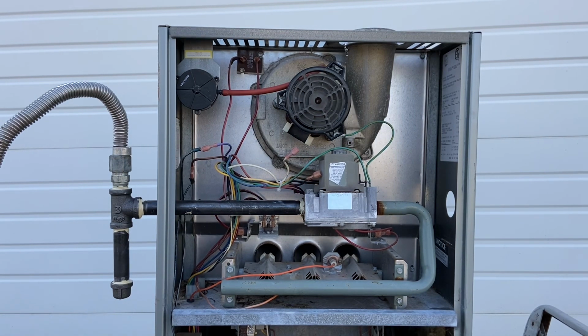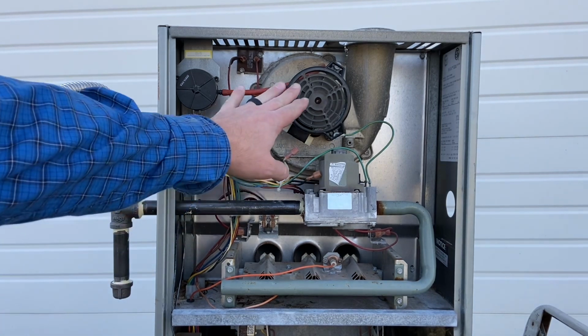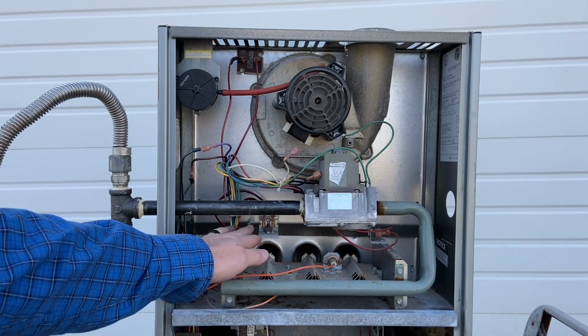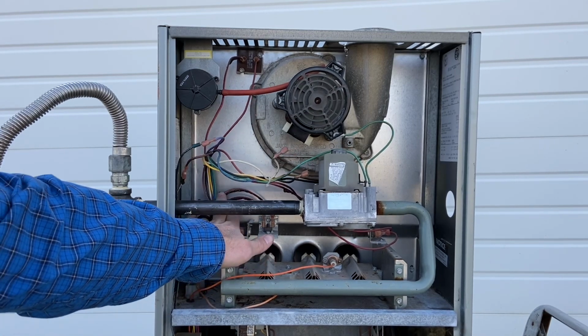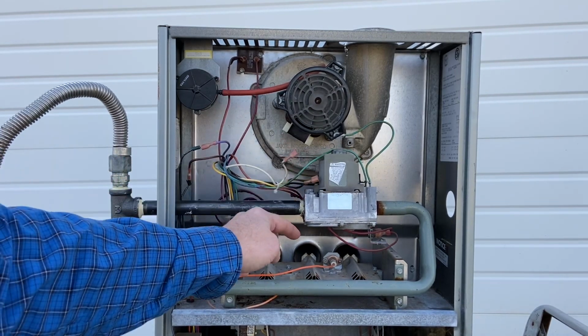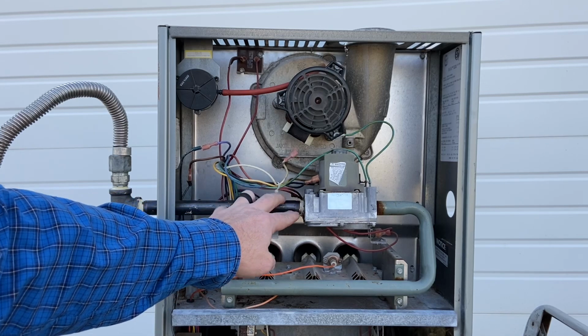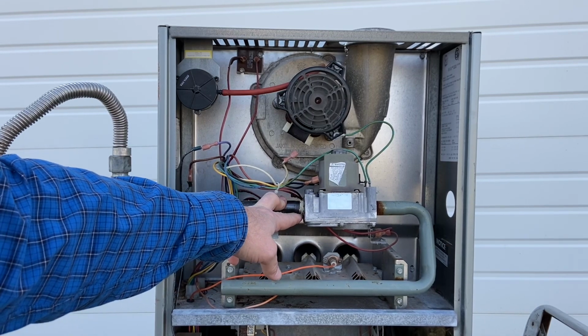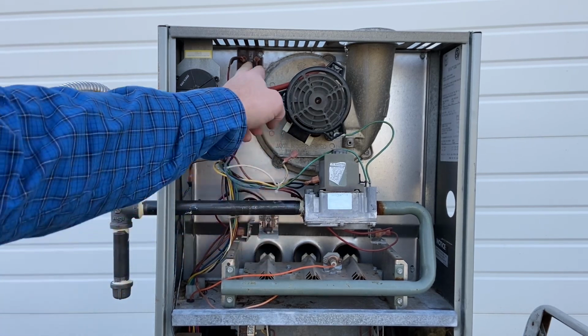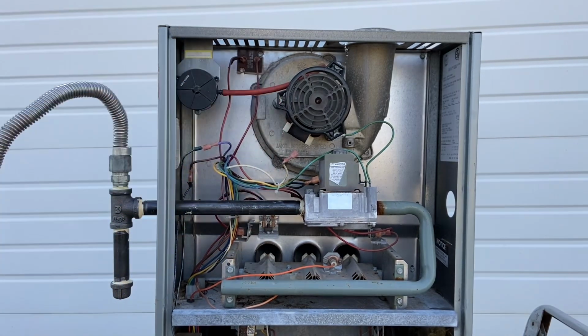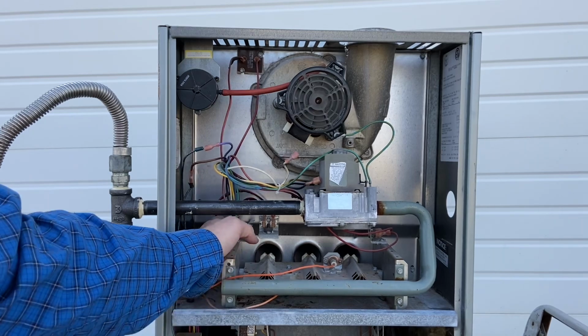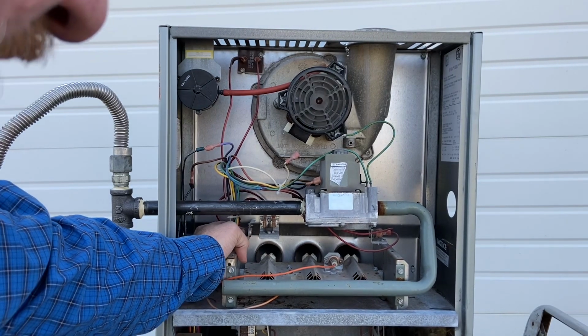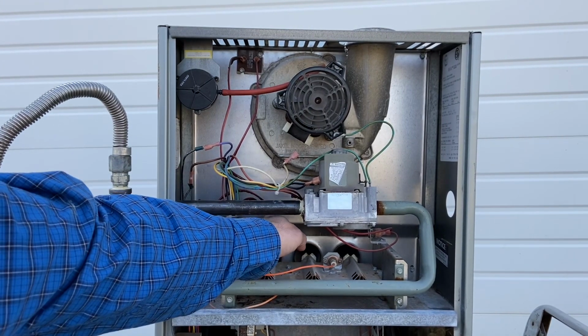So you can see there's a significant amount of time before the rollouts actually tripped on this furnace. That's how important this inducer draft motor is. We can see that there's a lot of charring going on. These wires have melted. They've melted here. There was a flame here because there was a small gas leak here where we didn't put new pipe thread compound on there to seal it. It burned all the way up to the top, and even our limit switch failed. It's all melted. The furnace is not running right now because these limits have tripped. They're manual reset. So if we push the button, we can hear them click.